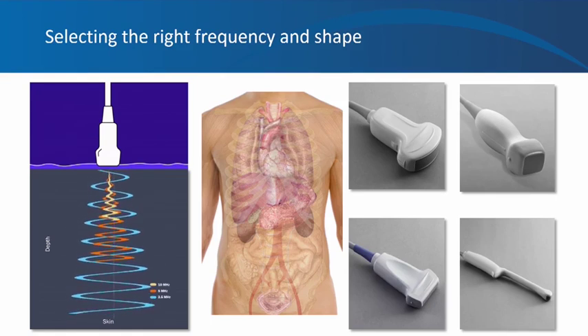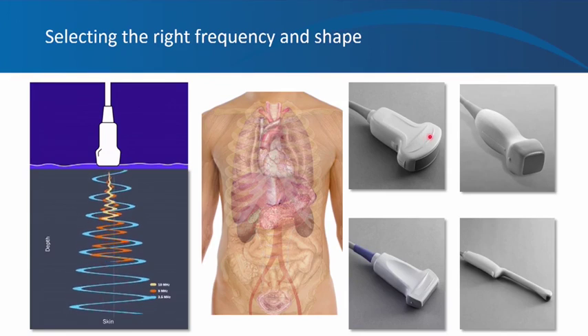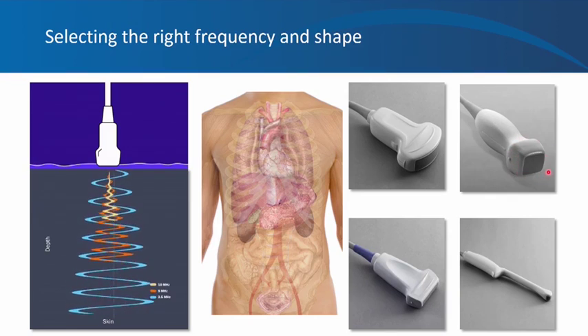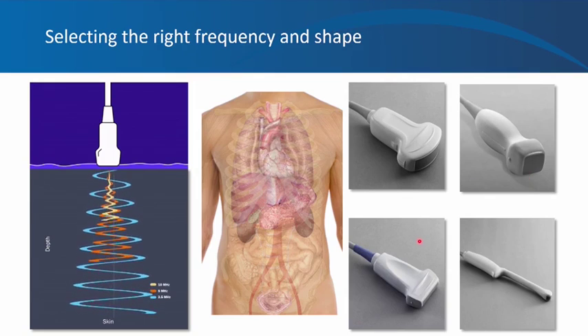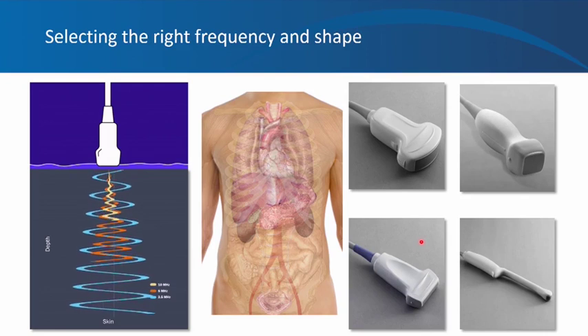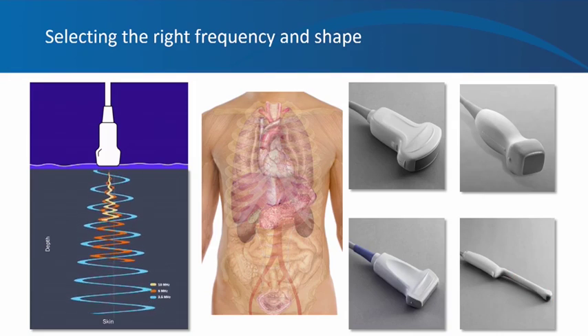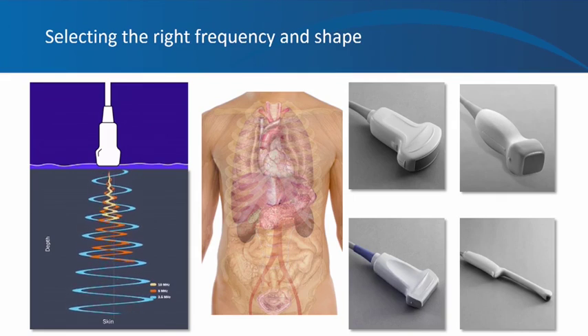The curvilinear transducer is used to image the abdomen; its shape allows imaging of larger organs. The phased array, or cardiac probe, has a small squarish mouth that allows maneuvering between ribs — it is also a low-frequency probe, so it can be used for kidney ultrasound if no curvilinear probe is available. The linear probe has high frequency and is used for vascular or superficial musculoskeletal ultrasound. The intracavitary probe is used for intravaginal, pararectal, or oral scans and offers high-frequency, high-resolution imaging.